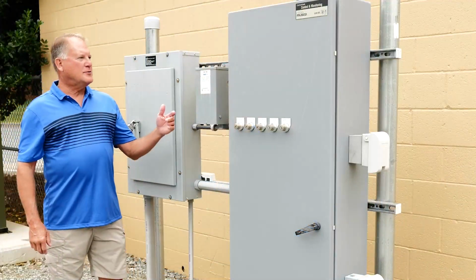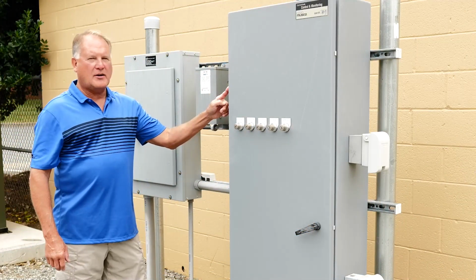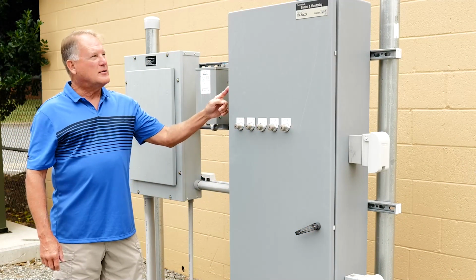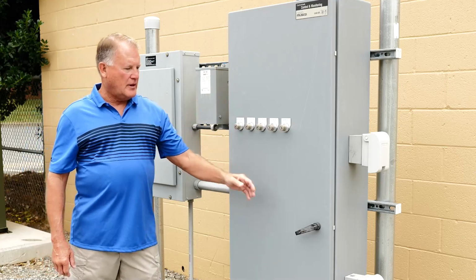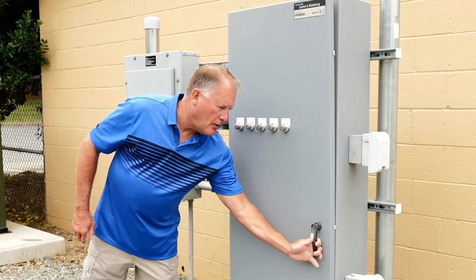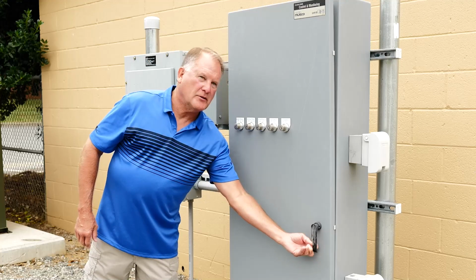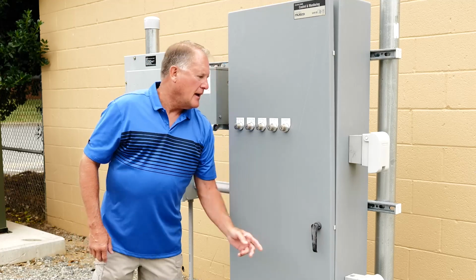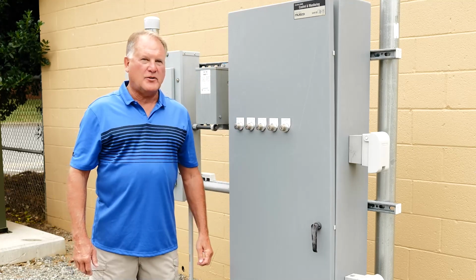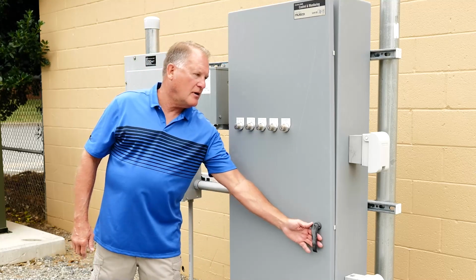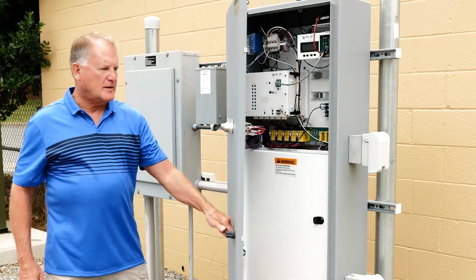Lighting contactors are the preferred method for controlling your lighting system. They can be controlled by either an on-site switch or a wireless remote control system. Moving on to our lighting control cabinet, which houses our lighting contactors. You can see the cover is in place. It has a lockable door where a padlock can be inserted. We've removed it. External key switches for manual operation and auto operation.